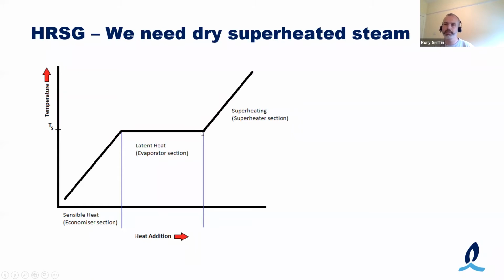And if you keep supplying heat, the temperature starts to take off very quickly here. So this is now superheated steam, and it's dry superheated steam. So that's what we want to get into the steam turbine. We do not want to put wet steam into the steam turbine because it can lead to damage of the turbine blades and corrosion. So what do I mean then by having a triple pressure system boiler, it's more efficient?